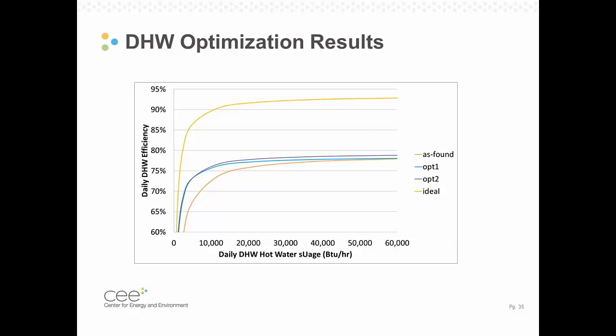So we saw that we were a little bit over-delivering on capacity. We're delivering about 60,000 BTU per hour. A standard gas water heater does about 40,000. So we looked at reducing the performance a bit.